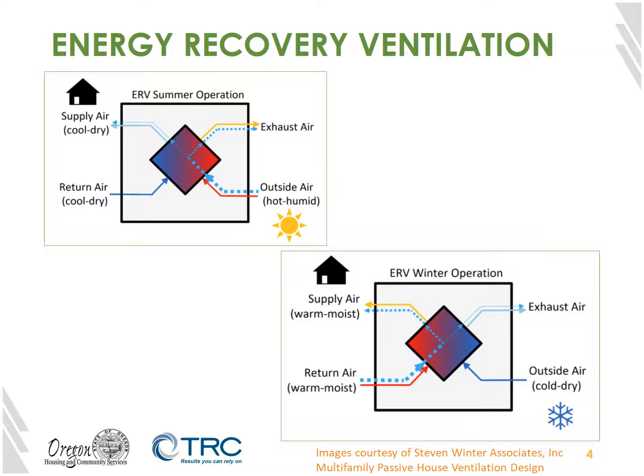For eastern Oregon, or at very high elevations, and when the buildings are very tight, an ERV in winter transfers both the heat and humidity to the supply airstream at the recovery core. As a result, the building may not suffer from too much dry air with winter operation of an ERV. Overall, ERVs can be slightly more efficient than HRVs as they transfer both the sensible heat as well as some of the latent heat through the moisture.